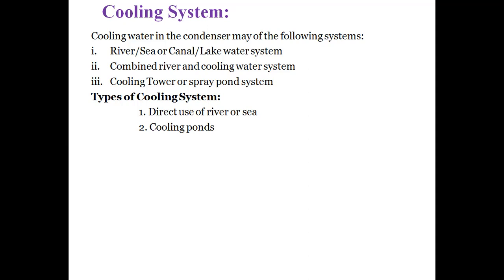So, the main steam condenser performs the dual function of removing the heat rejected energy from the plant cycle and keeping the turbine back pressure at least to the lowest possible level. So this rejected energy must be returned to the atmosphere. The main condenser does this by transferring the latent heat of exhaust steam to the water exposed to the atmosphere.